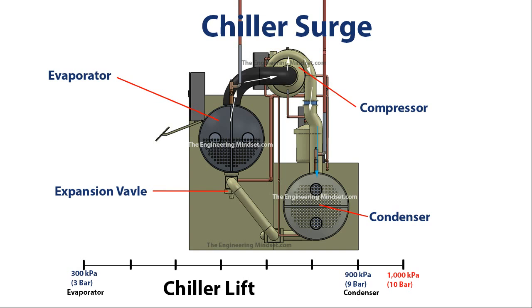Now let's say that the pressure in the condenser actually reaches 1000 kPa — 10 bar. That is much higher than the maximum pressure that can be provided by the compressor, and when the pressure in the condenser is higher than the pressure that can be applied by the compressor, chiller surge will occur. These numbers are just for example purposes — please check with your chiller manufacturer to find out what your surge line and your chiller lift are.